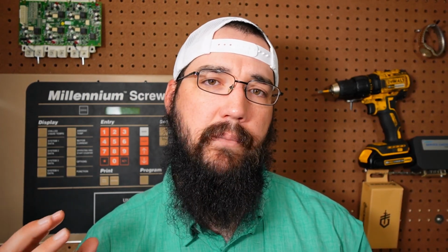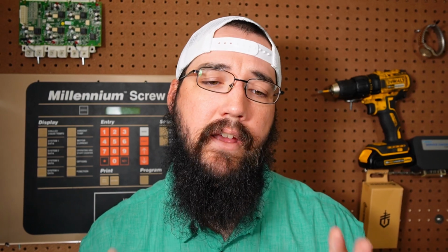It's just a personal preference to hook up in the middle and let everything draw to that central point, because otherwise, if you hook up at the outdoor, the gases in the atmosphere have to travel a lot further through the piping network in order to get pulled out of the system as a whole. So for me, it has worked well to find a central point and hook up there. But the critical thing is your micron gauge needs to go at the furthest possible place you can put it from wherever your pump is, which is also another fundamental of regular vacuums.